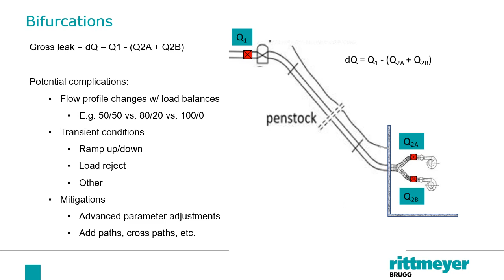The next interesting challenge comes with pump storage systems. If you look at this example, and it's typical of many of them, you'll see that in generate mode, the upper flow meter is located close to an intake, and it's going to see a lot of flow distortions, again, that vary over the flow rates.